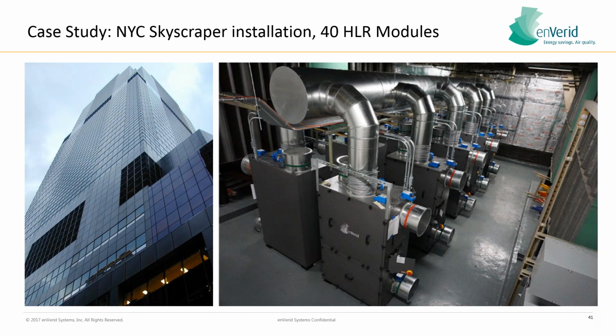So because this system is a 24/7 application, we regenerate these systems, we stagger the regeneration and exhaust that CO2 laden air directly outside the space. Okay, so we're scrubbing air within the mechanical room, we're placing that air back into the mechanical room, and the fan wall is pulling that cleaner air back through the system.